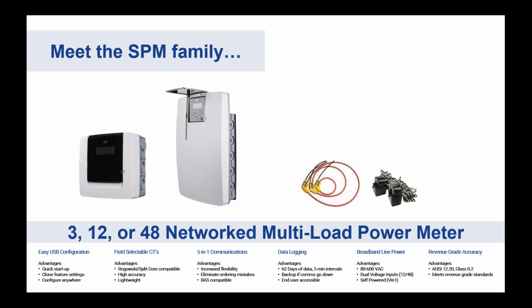With our meters, one thing that was important to us is to limit the amount of SKUs people had to carry in inventory or remember to buy. So with that, we tried to pack everything that we could into one SKU for the 3, one SKU for the 12, and one SKU for the 48. And with that, you can field select CTs, whether they're split core, Rogowski, or even existing CTs that you may have out in the field up to 2 volts. You can configure those CT inputs for.